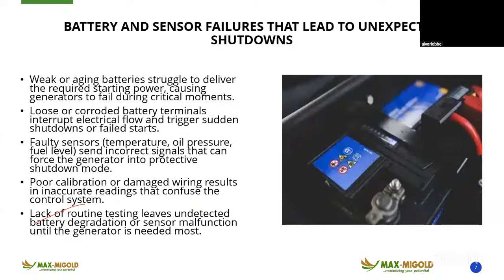Poor calibration or faulty sensors, like temperature, oil pressure and fuel level sensors, send incorrect signals that can force the generator into protective shutdown. So if these sensors are malfunctioning and you don't pay attention to them, the generator might be working and suddenly it will shut down. If you check, you will find out that the water level is there. Maybe there's no proper contact between the water sensor and the water because of some level of depth. Ensure these are checked on a regular basis.